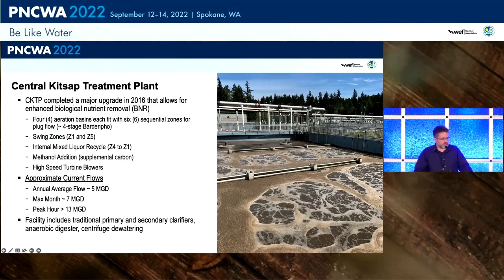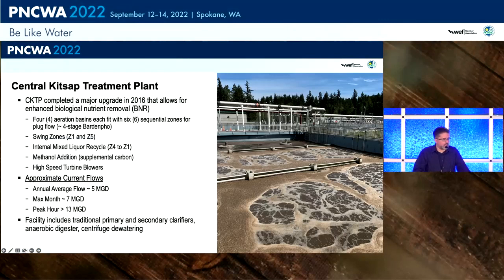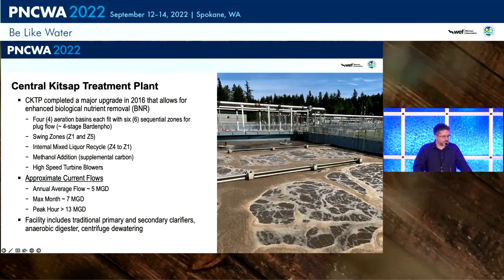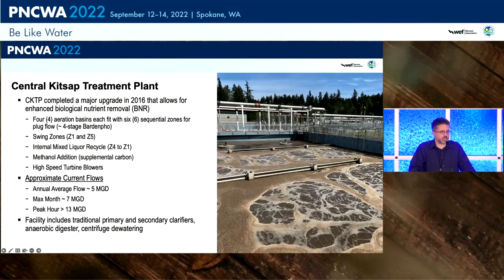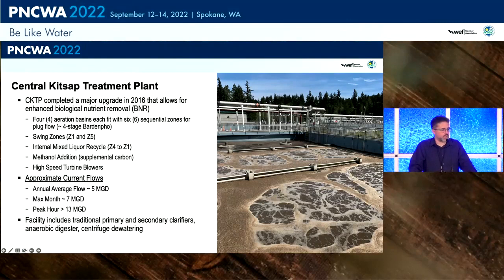The Central Kitsap Treatment Plant is Kitsap County's primary treatment facility — they have four treatment plants and this is their largest. It completed a major upgrade in 2016 that allowed it to do enhanced biological nutrient removal. It has a four-basin system with six sequential zones in each basin — basically a four-stage Bardenpho flow — with swing zones, internal mixed liquor recirculation, methanol addition, and upgraded blower technology. So the liquid stream had a lot of work done and a lot of tools available to it.